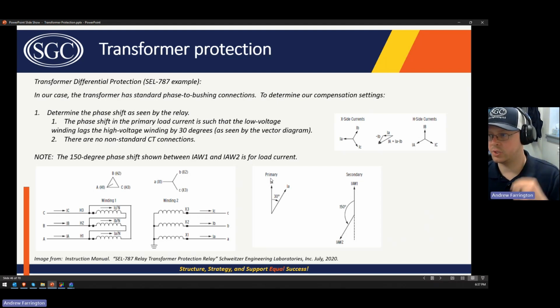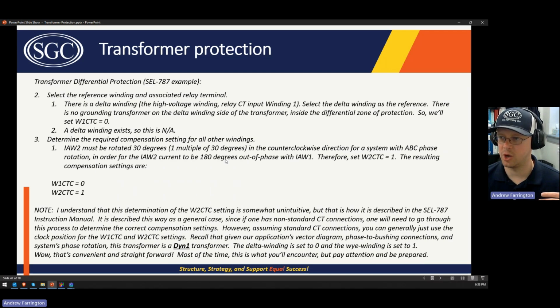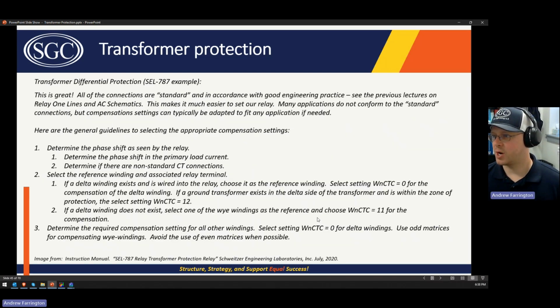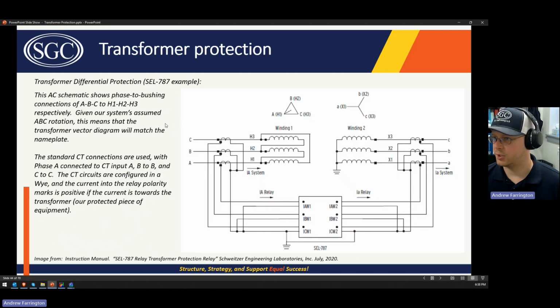Okay. So this is how I think of it, right? The IA, capital A, is the primary current, and the Y winding current lags by 30 degrees. That's the 1 o'clock position. This is 12 or 0, and then you have the 1 o'clock position, so you just set it to 0 and 1. Most of the time, that's all the thought that goes into it. You just need to be aware of the other times when you might not have a standard CT connection or a non-standard transformer phase shift. Okay. That's why it goes through this long explanation. What they're driving at is for load current through the transformer. Say current going through this phase into this winding and then coming out of this winding and going into that phase.